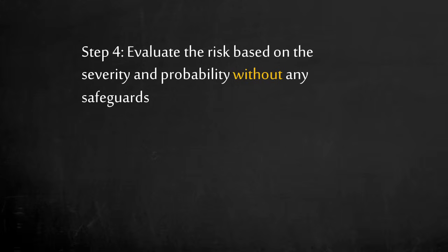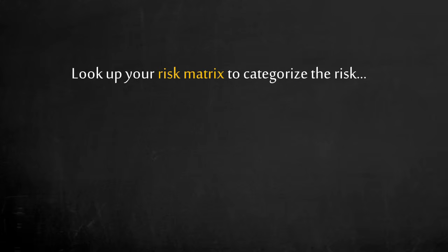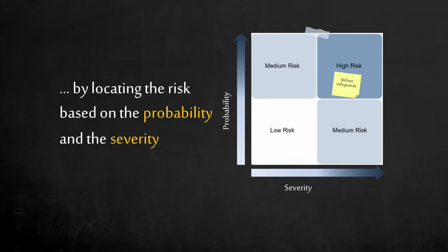Step 4: Once a consensus is reached, evaluate the risk based on severity and probability without any safeguards. Let's say our scenario has a high probability of control valve failure and a high severity due to possible fatality. The definition of high probability and high consequences is defined in your corporate risk matrix. Look up your risk matrix to categorize the risk. To keep this example simple, there is high probability and high severity on the risk matrix. This is considered a high risk and not acceptable. What can be engineered to reduce this risk?